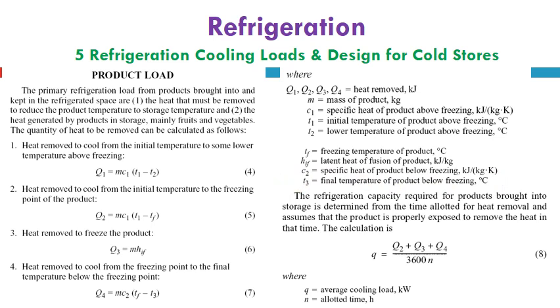The refrigeration capacity required for products brought into storage is determined from the time allotted for heat removal, and assumes that the product is properly exposed to remove the heat in that time. So for the calculation, to express power instead of kilojoules, we have to generate kilowatts to estimate this product load as a power in a certain time to be cooled, maybe 1 hour. So we will take 1 hour.